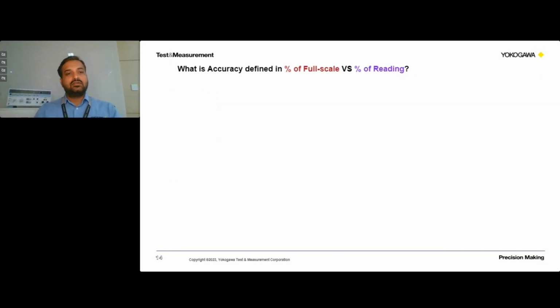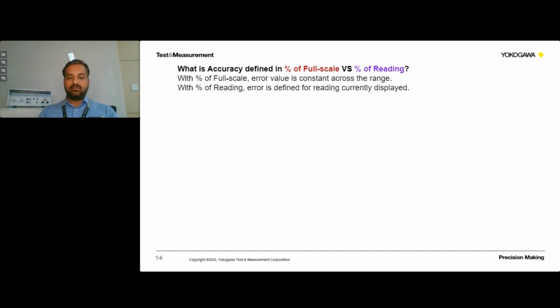So next we will discuss accuracies defined in percentage of full scale and percentage of reading. When we come across any instrument, whether it can be DUT or it can be master, we always see the specifications for accuracy defined in percentage of full scale and percentage of reading. With percentage of full scale, the error value is going to remain constant across the range. We will have a standard error across the defined range for that particular DUT. Whereas with percentage of reading, the error or deviation will be defined for that particular value which is being displayed, or for that particular reading which is getting displayed.